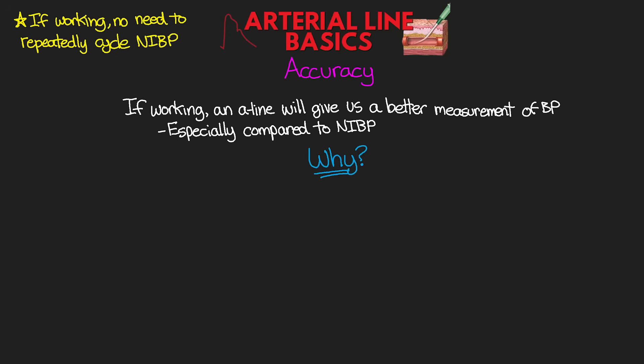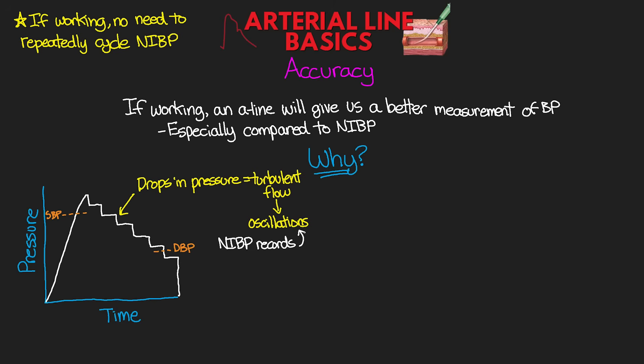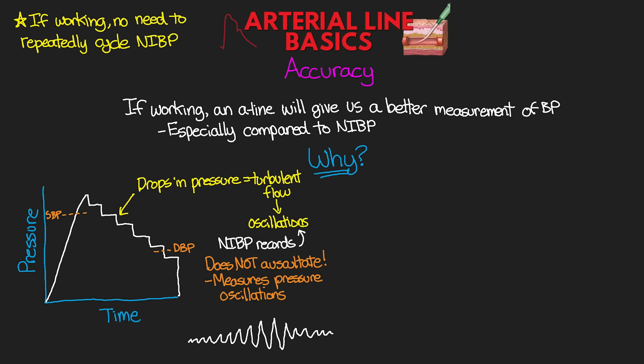To explain this, I'm going to draw out a graph here looking at pressure versus time. As you've seen and heard, the non-invasive blood pressure inflates past the patient's systolic blood pressure — this is part of the discomfort for the patient. It then releases a little pressure step by step until it gets past the diastolic pressure. This drop in pressure creates turbulent flow, which oscillates against the arterial wall. The non-invasive blood pressure cuff records these oscillations in pressure. Unlike when we auscultate a manual blood pressure, the non-invasive isn't auscultating anything — it's just measuring those pressure oscillations. These oscillations start small, grow to a maximum, and then drop back off.